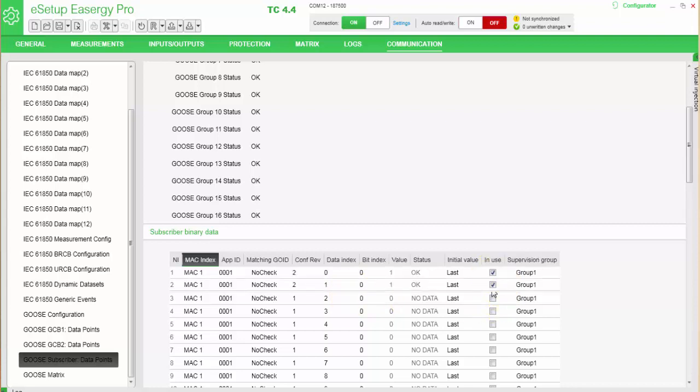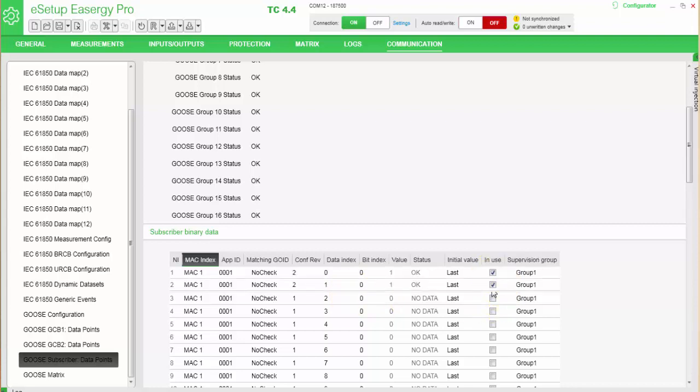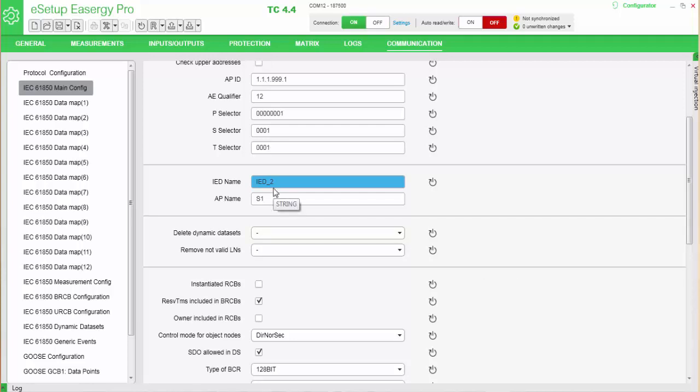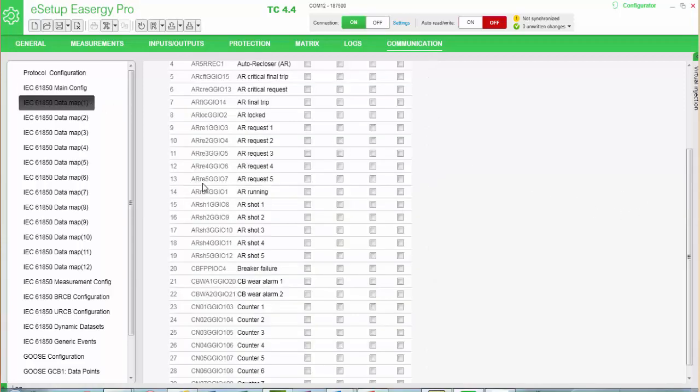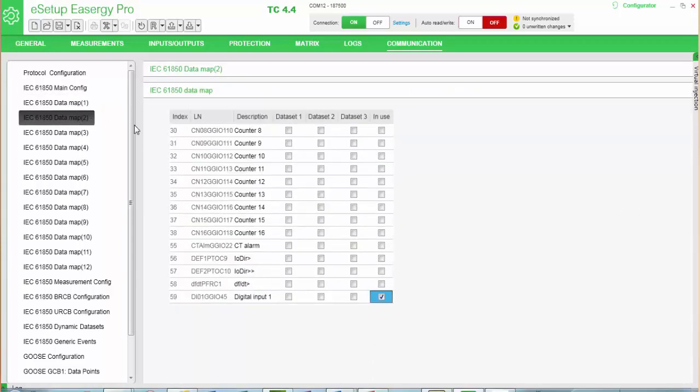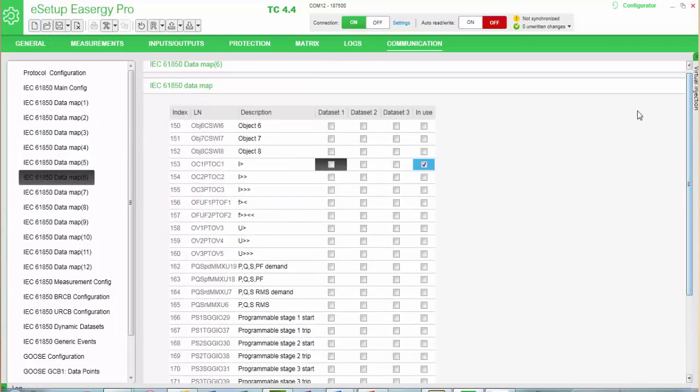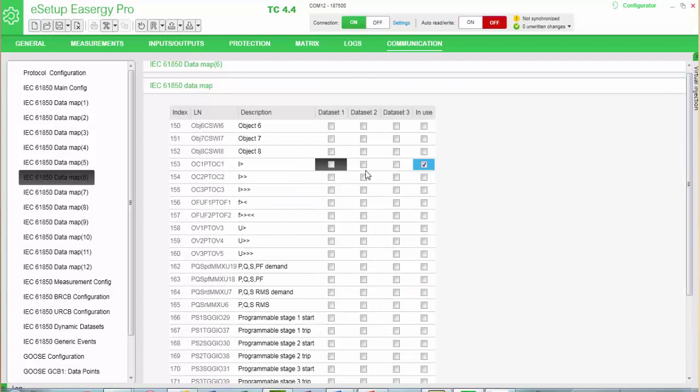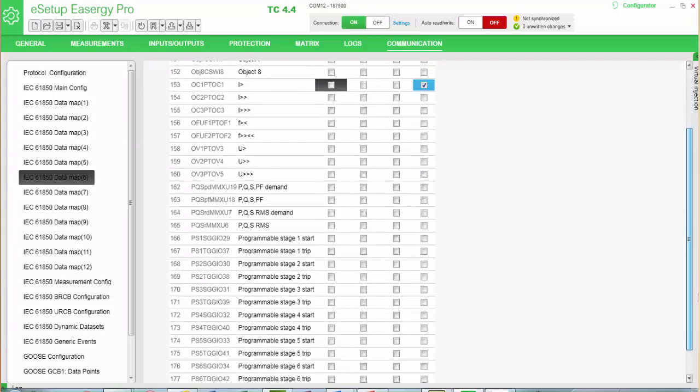In the publishing relay, we will, in the main configuration, define the IED name. In this exercise, we will use the IED_2. In the data map page 2, we will use the digital input for publishing. In this case, we don't need to define it to any other dataset, we will just put it into use. For overcurrent function, we also want to publish. We already have it in use. We don't need to define it into the dataset in this relay.